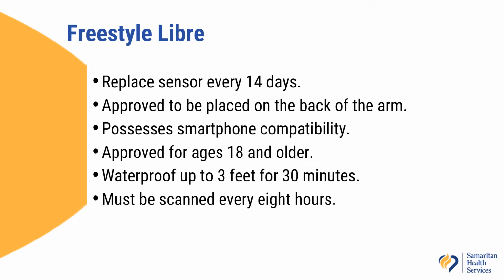For the Freestyle Libre, you have to replace the sensor every 14 days, and it's worn on the back of the arm. This can connect with your smartphone, so you can use a monitor or a smartphone with this. It's approved for ages 18 and up. It is waterproof up to 3 feet and for 30 minutes, so you can shower and you can do some shallow swimming for a short period of time. It must be scanned every 8 hours with either your smartphone or monitor.